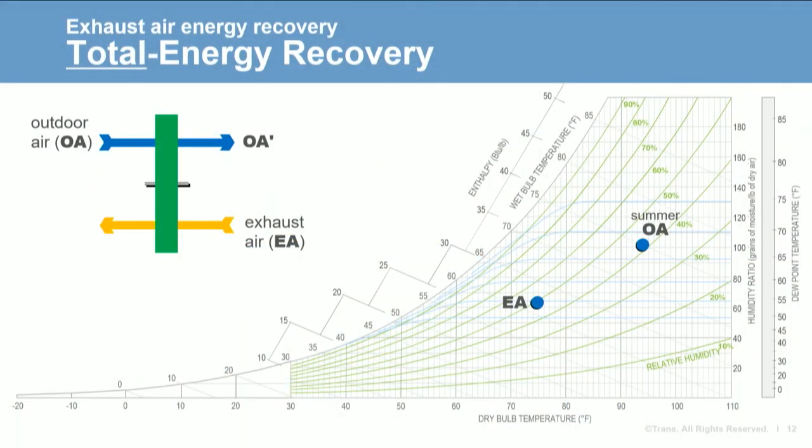Now let's compare that with a total energy recovery device operating at the same conditions. When it's hot and humid outside, total energy recovery transfers sensible heat cooling the outdoor air, but also transfers water vapor from the humid outdoor air to the drier exhaust airstream, drying the entering air. The result is that total energy recovery lowers the enthalpy of the entering air much more than sensible recovery alone, resulting in a greater reduction in cooling load in humid climates.